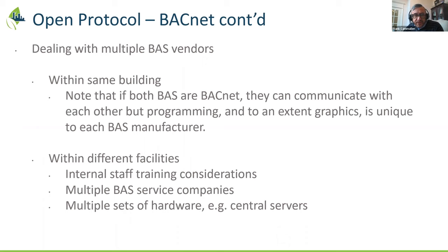I want to talk about BAS with multiple vendors, both within the same facility and across different facilities. Within the same facility, if both BAS manufacturers are BACnet, they can definitely communicate with each other, but be mindful that programming and graphics are fairly unique to each BAS manufacturer.